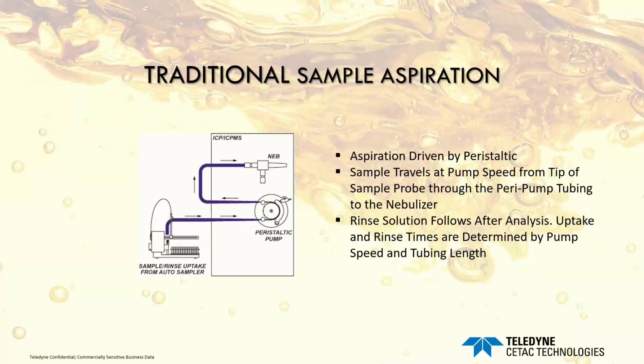Traditional sample aspiration is driven by the peristaltic pump on the ICP. Sample travels from the tip of the sample probe to the nebulizer at the speed of the pump. Whatever the speed of the pump is running, that's how fast your sample is moving. The rinse solution follows after analysis, and the uptake and rinse times are all determined by the pump speed and the length of the sample tubing.